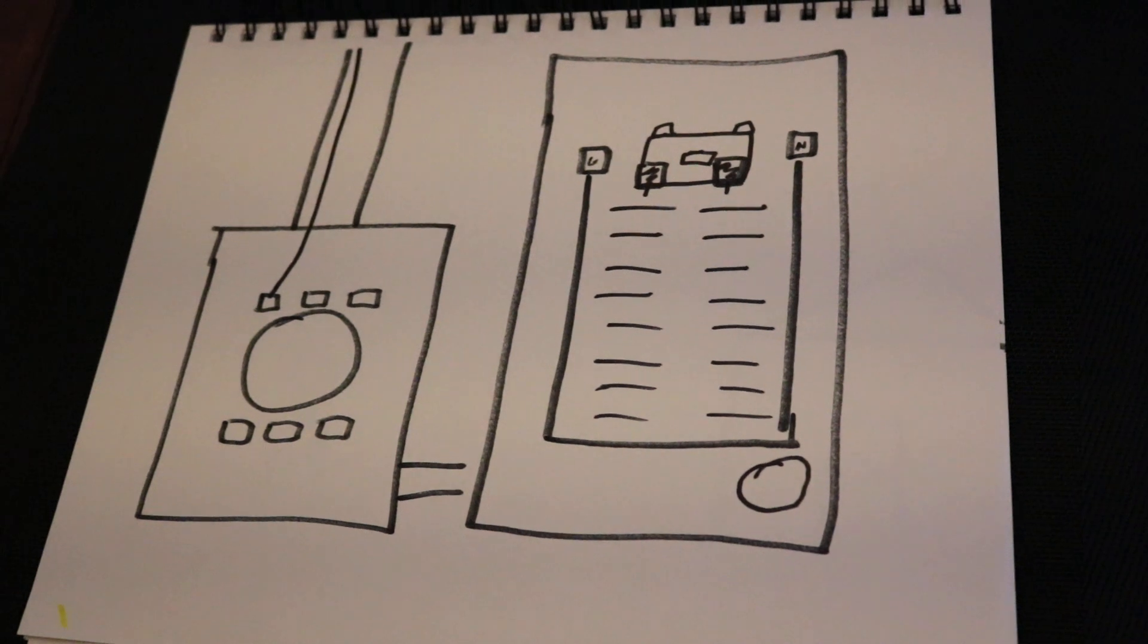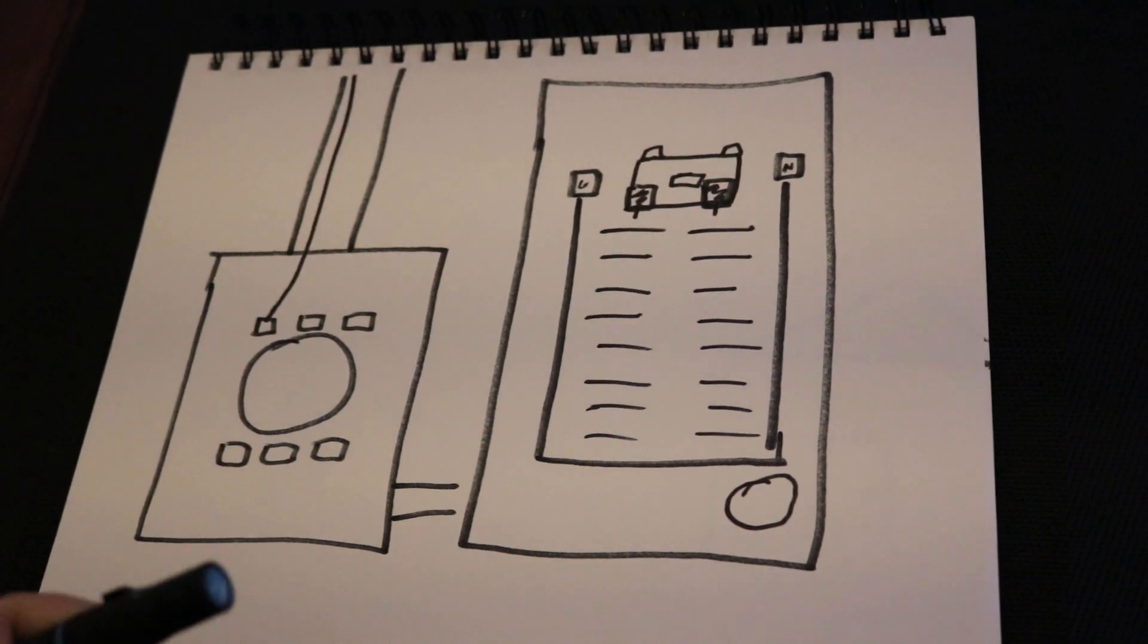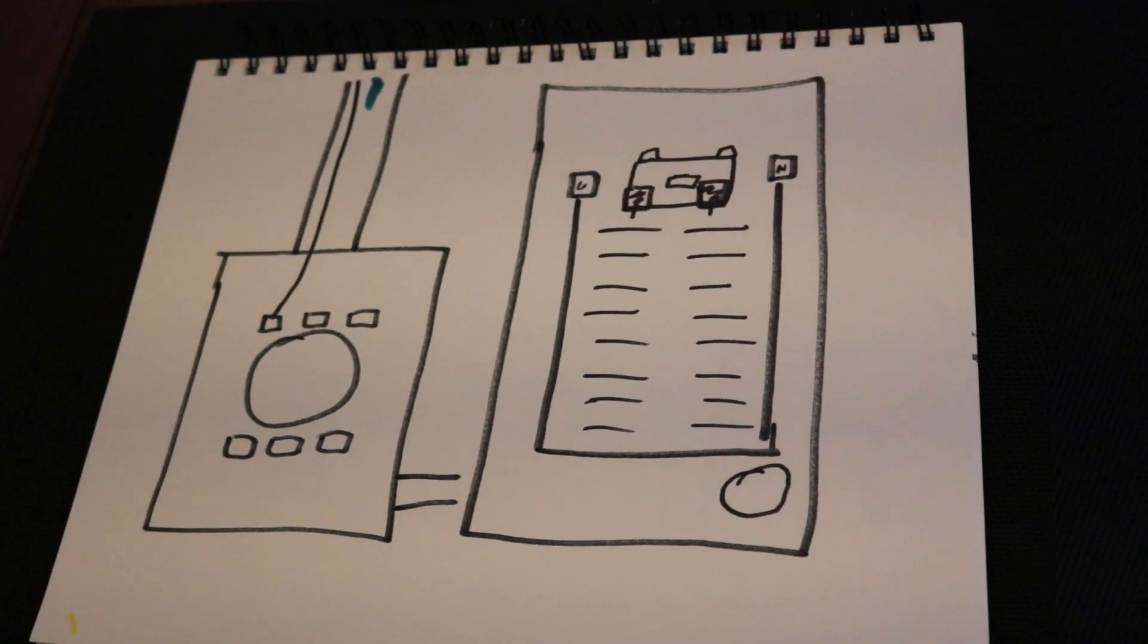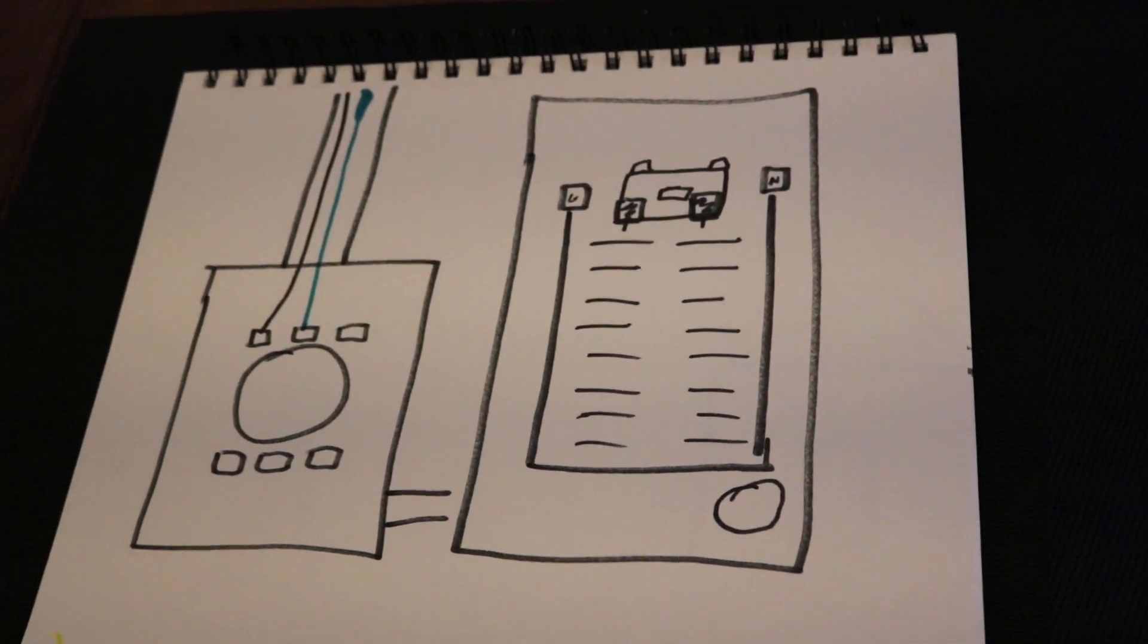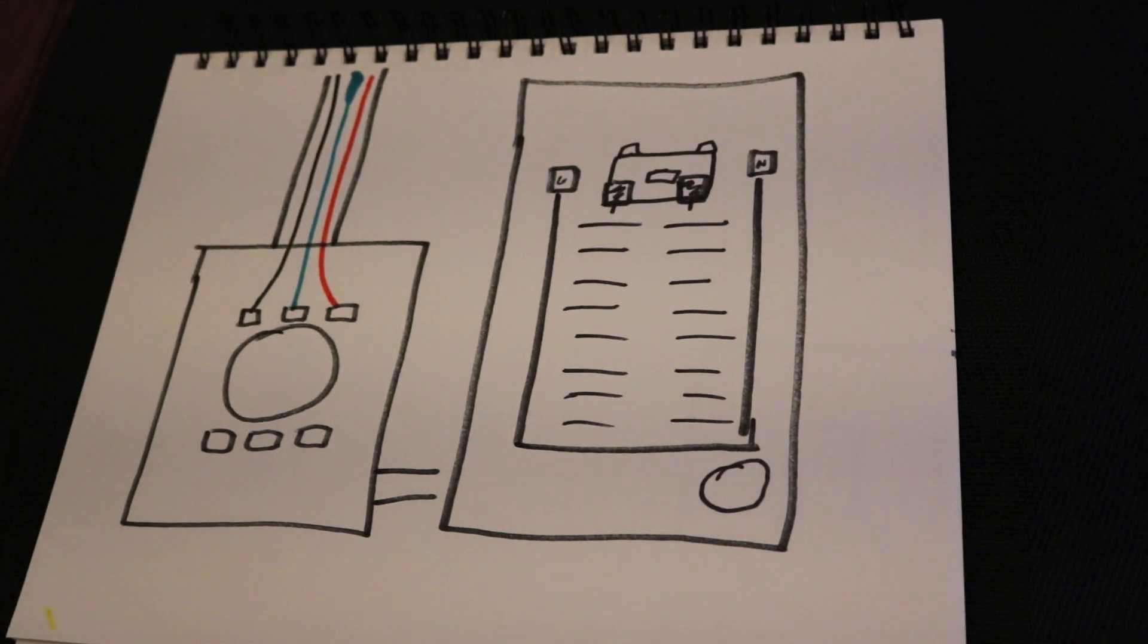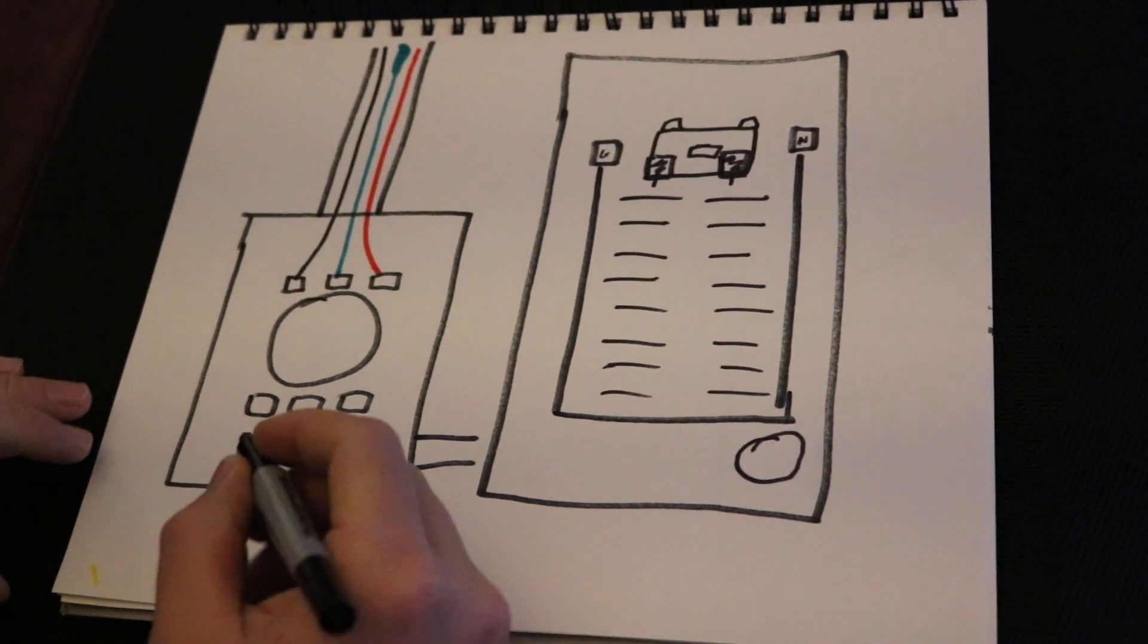There's going to be three conductors coming in. It's going to be black, and in the city of Boston where I live it's red. I'm going to use a blue pen here for the neutral wire. This would be your white wire and here's the red. So those are your three incoming lines going to the top of the meter to the line side, and then from here we're going to go to our panel board.